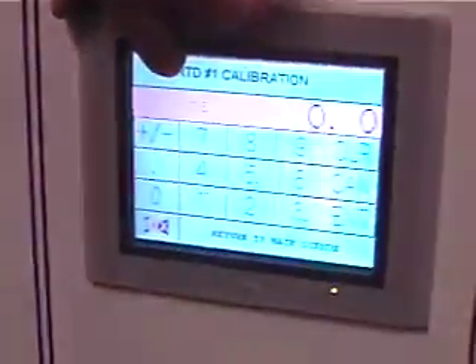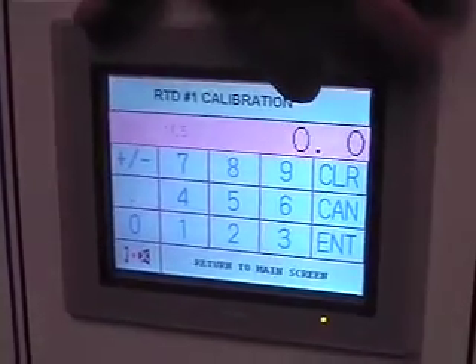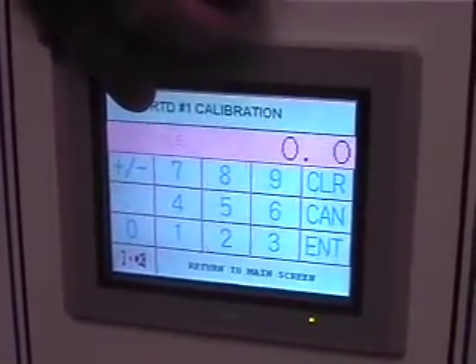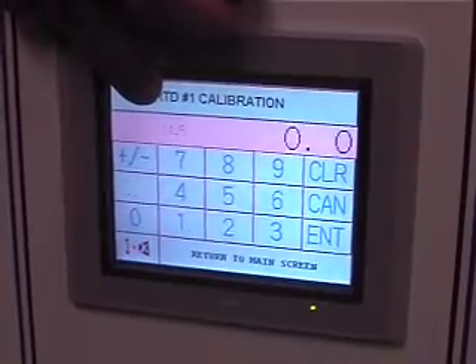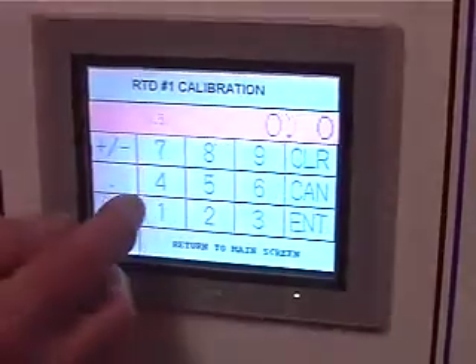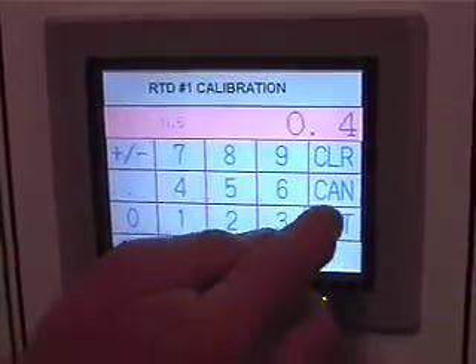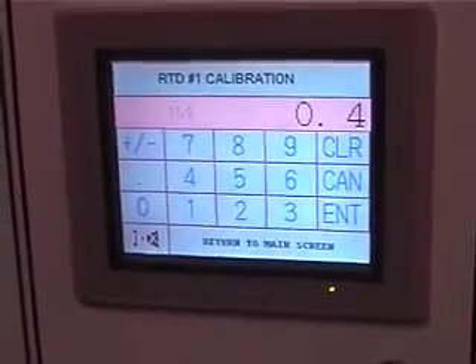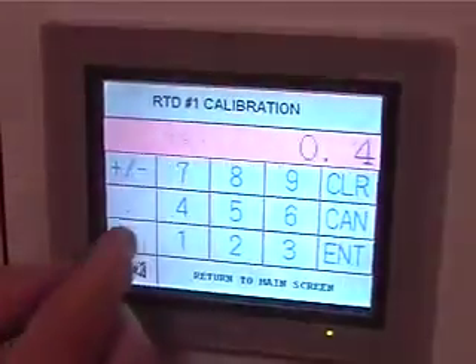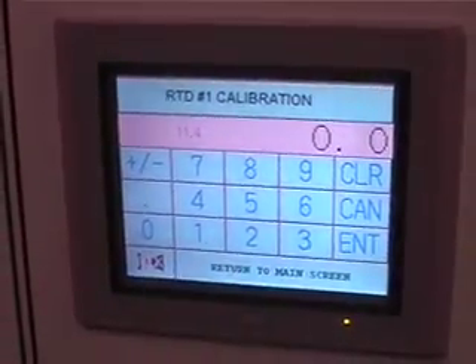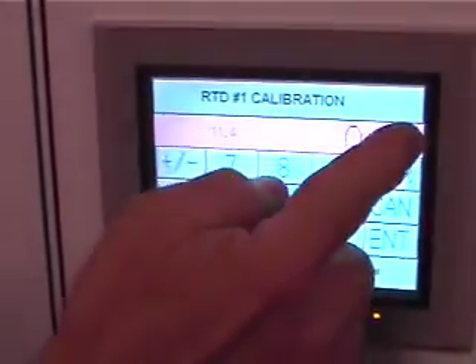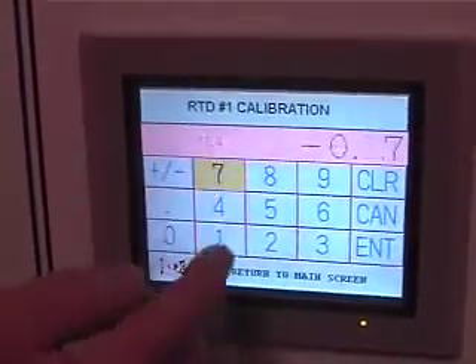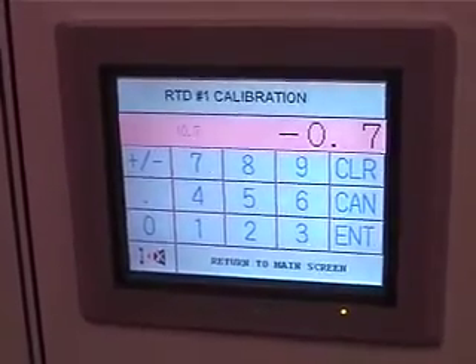This is the temperature that the RTD thinks it is. And this is your offset calibration. So if we stuck our Fluke in there and it said, no, it's 11.9, we would hit that and go 0.4 and enter. And now it's 11.9. Simple as that. A lot easier than Honeywell, I can tell you that. Same thing in reverse. If they thought it was 10.7, you go minus 0.7, enter, and now it's 10.7. Okay.